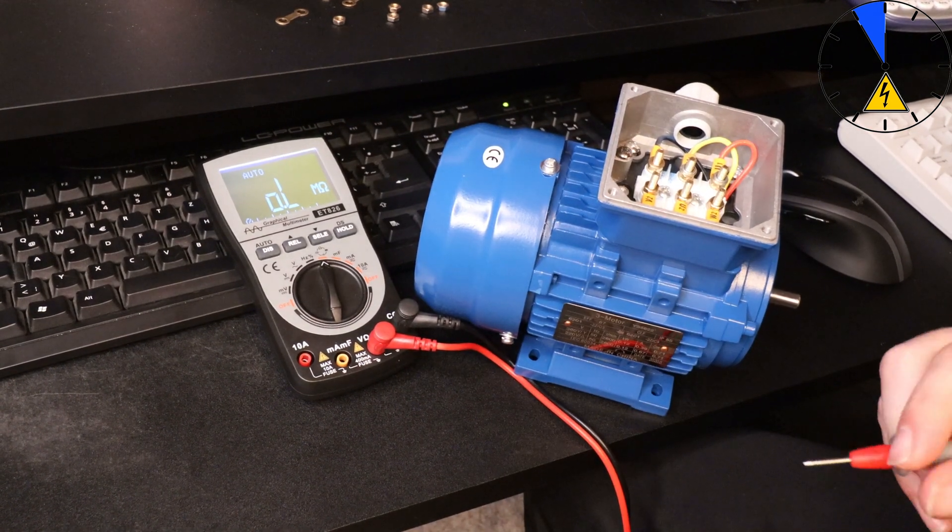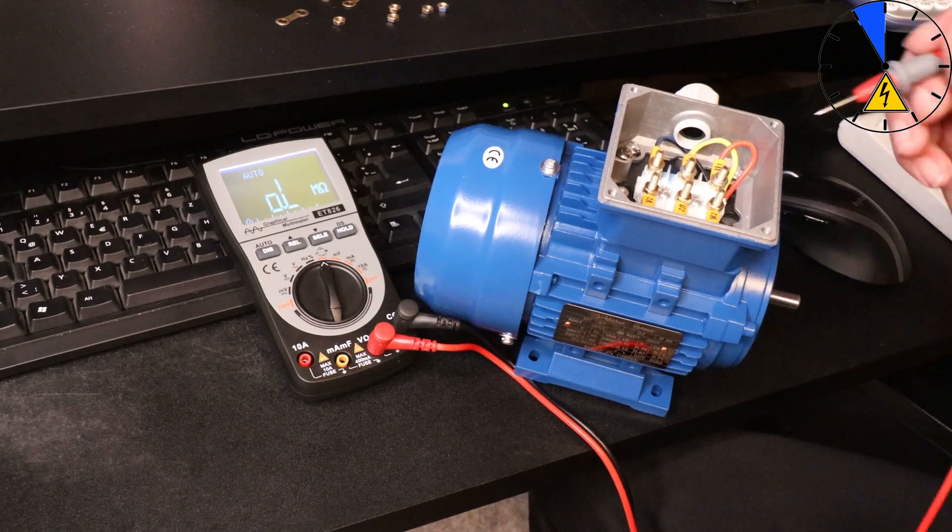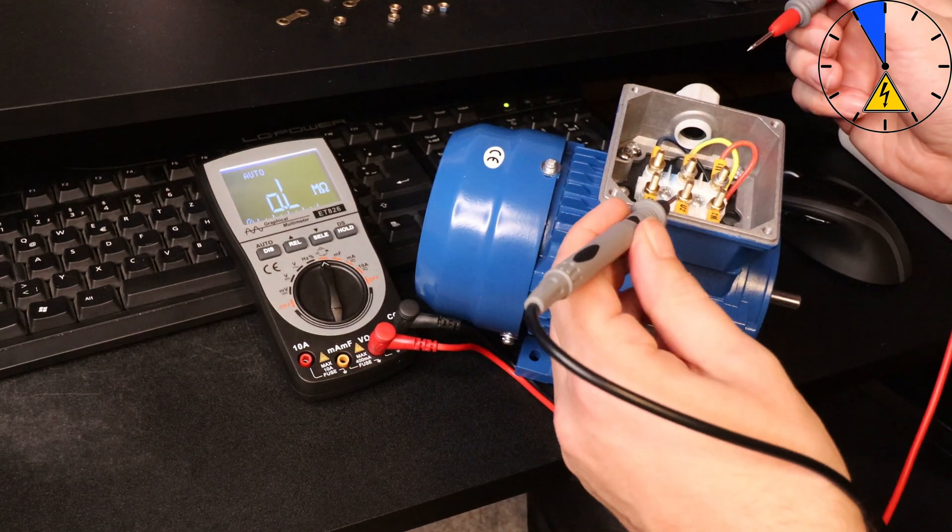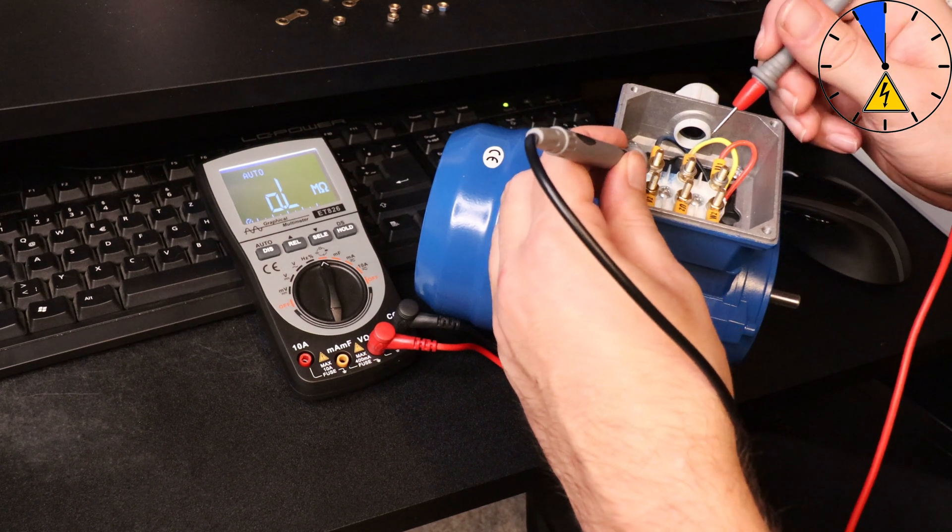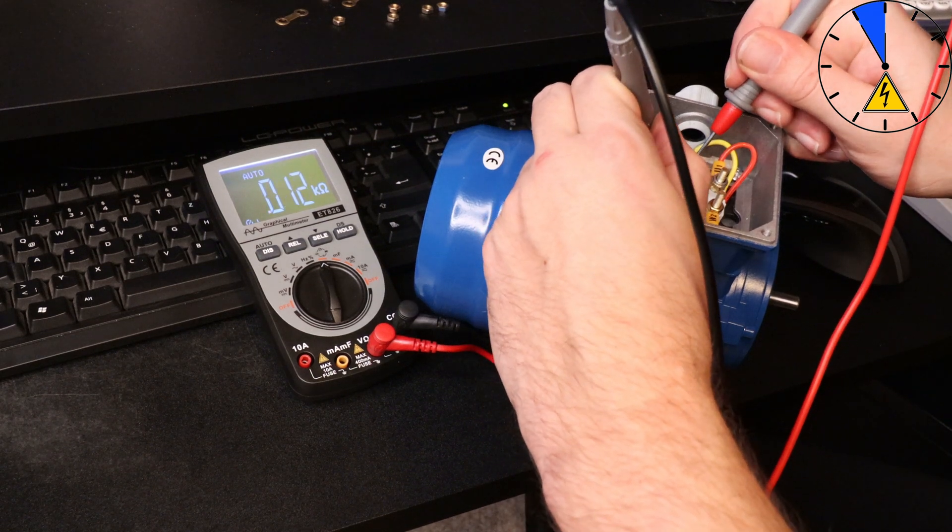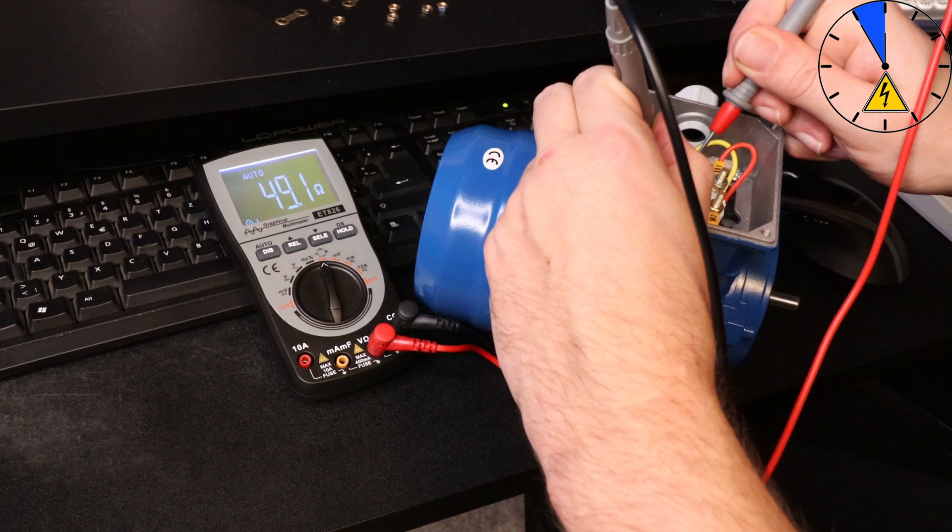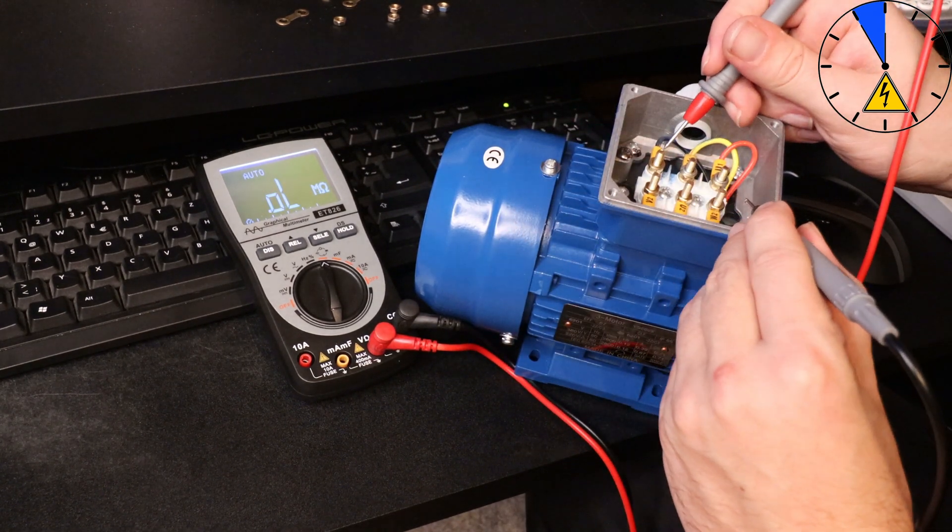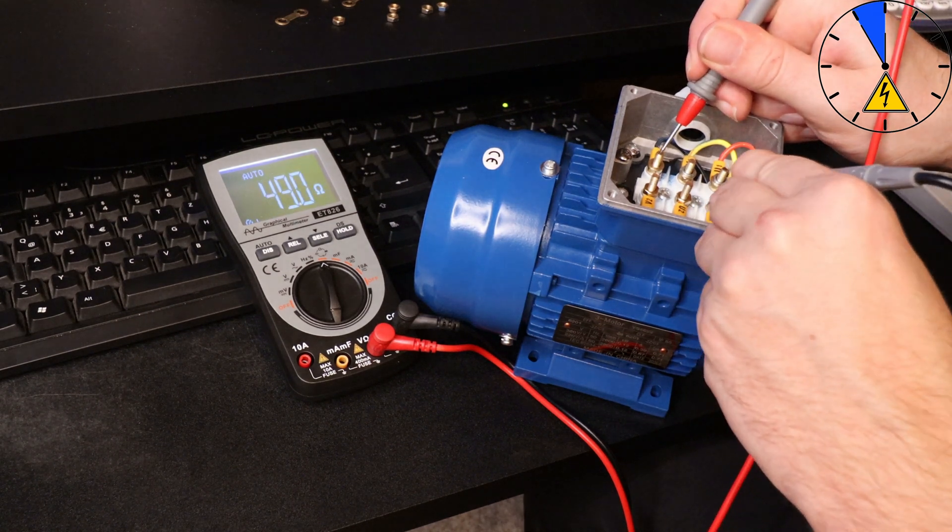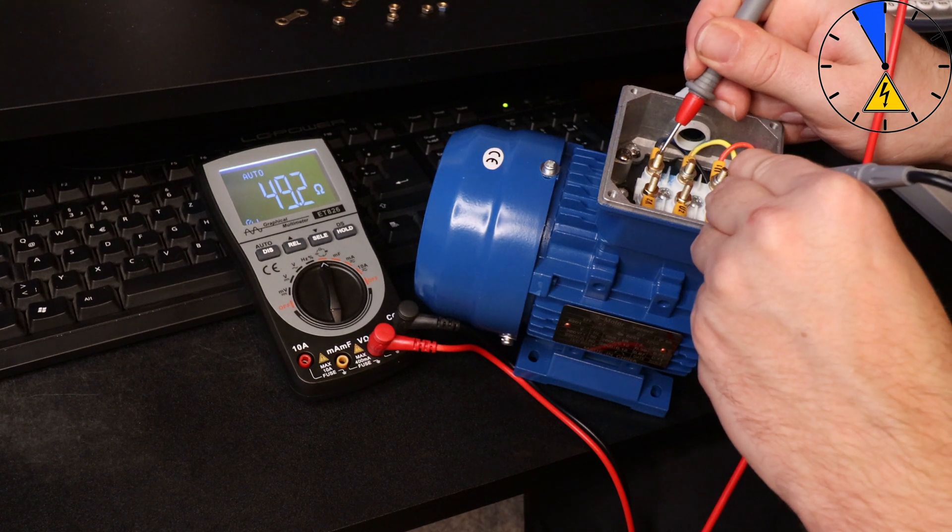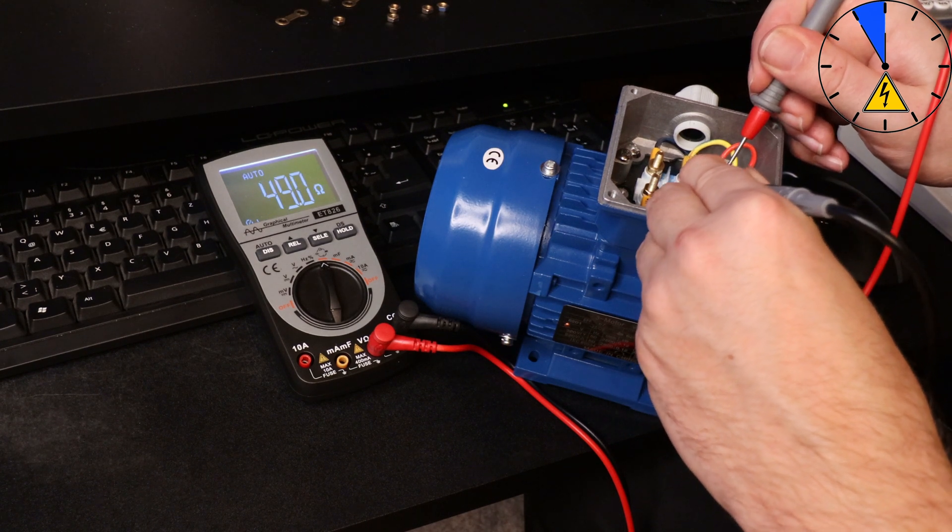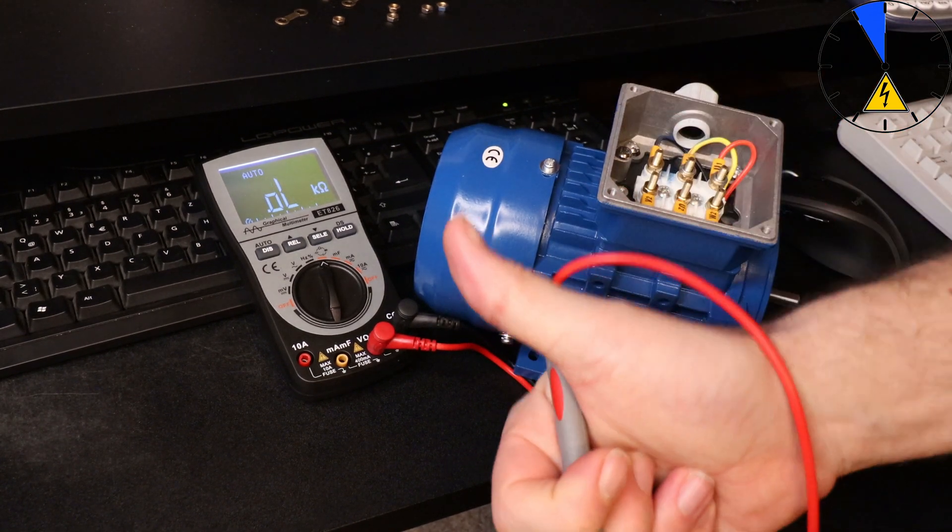The next test is every resistor of these three coils has the same resistance. Then I go from V2 to V1 and here we have 49 ohm. Then from W1 to W2 and the resistance is 49 ohm. And then from U1 to U2, 49 ohm. This test passed.